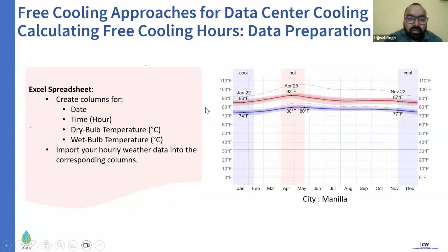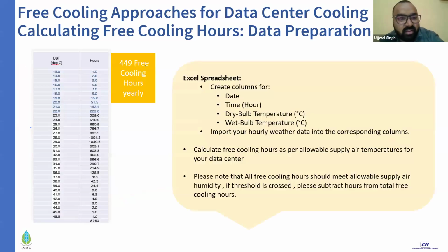Now what you need to do is find out the allowable supply air temperature to your data center. From the weather file, you need to find the dry bulb temperature and the number of hours in the year for which that temperature prevails. For example, 31 degrees Celsius prevails for 603 hours in the year, and similarly I have plotted the whole trajectory from 13 to 45.